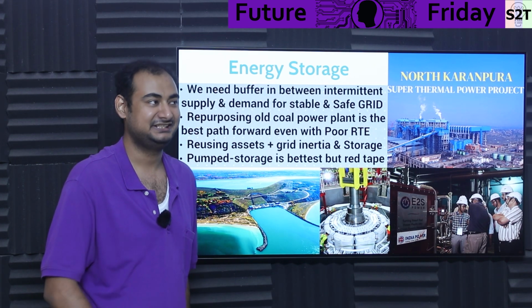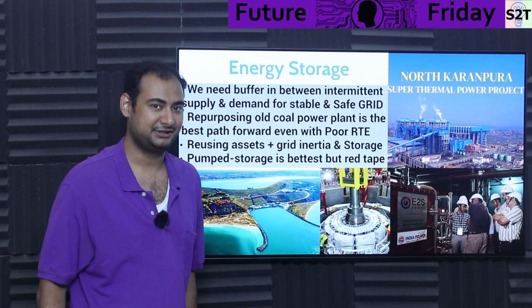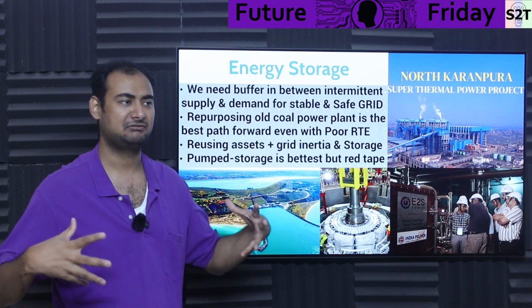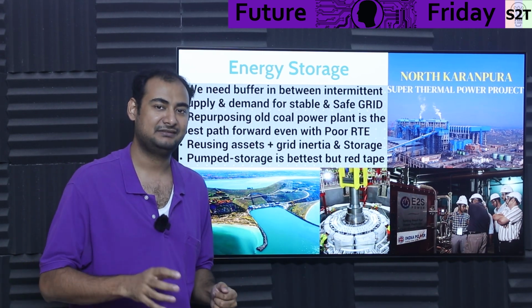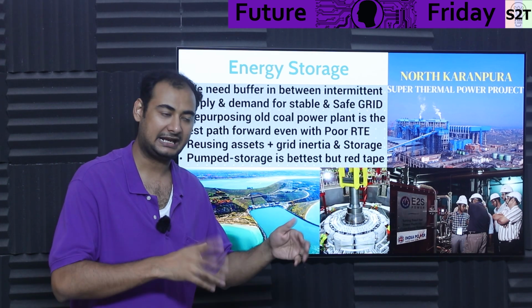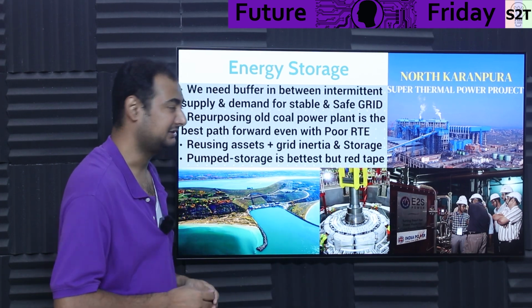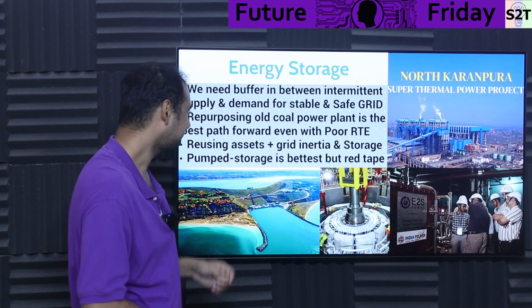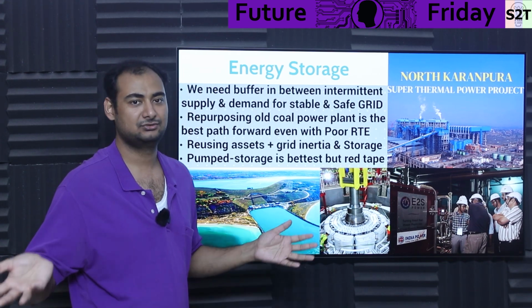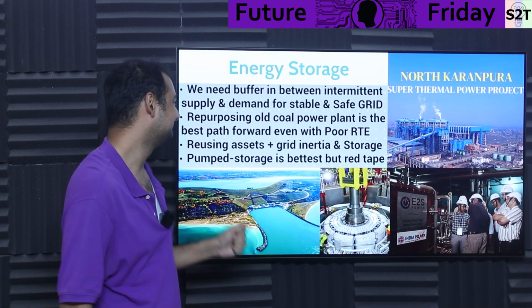That's not that much, you need almost half of what you are consuming. So even if tomorrow you have like 10 gigawatts of solar, you want at least 5 gigawatts of spinning inertia, not the actual generation, but inertia you need. And even 5 would be cutting it too close. That's for bad days. For good days, you do not even notice. For bad days, you do notice.